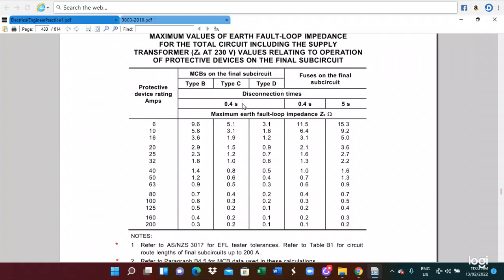In the meantime, you can also use a fuse. Sometimes circuits are protected by a fuse. The HRC fuse operating time is 0.4 seconds. A normal fuse is 5 seconds. So we have to select the appropriate circuit breaker or fuse and set the protective device rating.